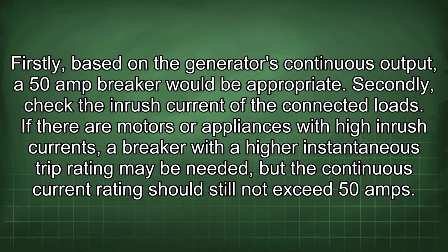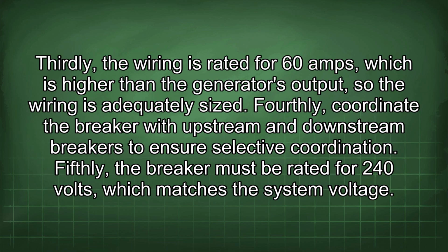Secondly, check the inrush current of the connected loads. If there are motors or appliances with high inrush currents, a breaker with a higher instantaneous trip rating may be needed, but the continuous current rating should still not exceed 50 amps. Thirdly, the wiring is rated for 60 amps, which is higher than the generator's output, so the wiring is adequately sized. Fourthly, coordinate the breaker with upstream and downstream breakers to ensure selective coordination.